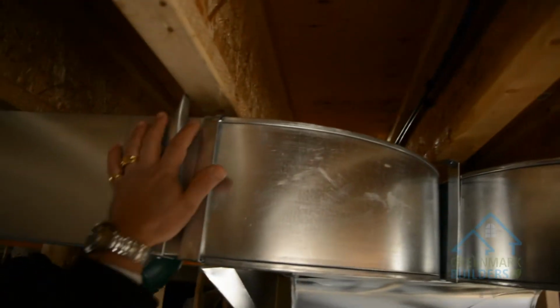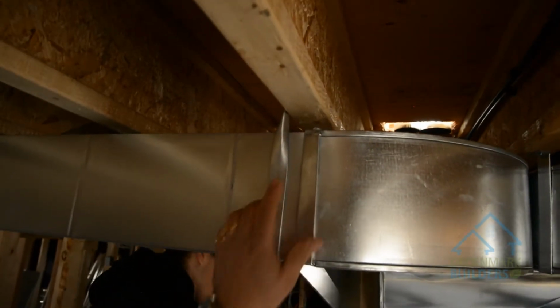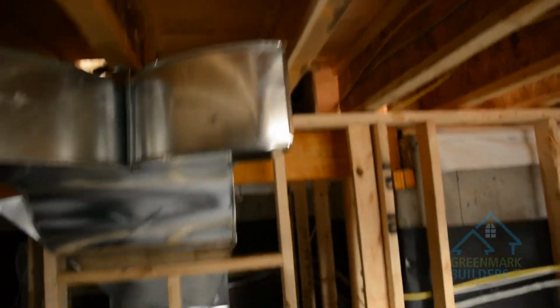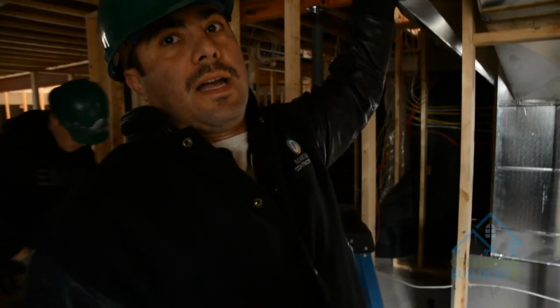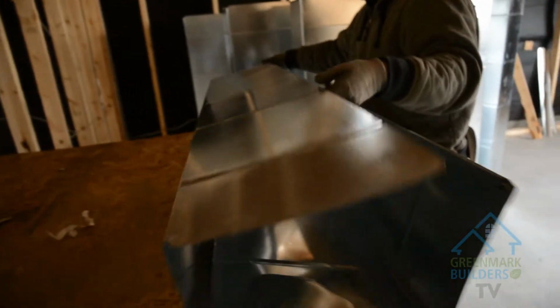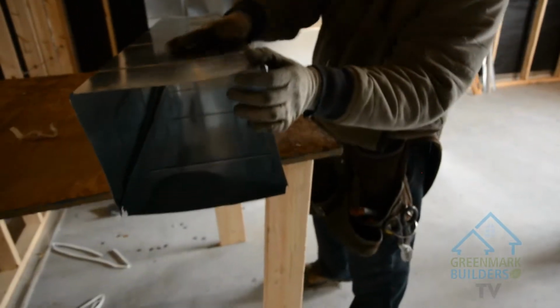Also, when they set the rectangular ductwork, you see the bracket here sitting 1 inch from the joist. You have to have clearance on the supply air. For the return air, you sit it tight, right against the joist.